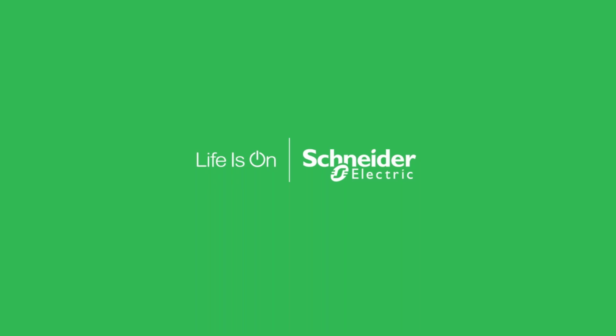Again, that's a great question. No licensing fees whatsoever. So when you buy a room controller, doesn't matter what room controller it is, whether it's this one or any of the other 8000 series, there's no licensing fees with it whatsoever. You just buy it, it's yours, you own it. Now, with that said, if the computer server on your BMS side has a requirement for licensing any of those BACnet objects that come out of it, that's something completely separate. But as far as the room controller goes, it doesn't care. It's a device. It is freely available. All the BACnet objects that are built into it are yours to use.